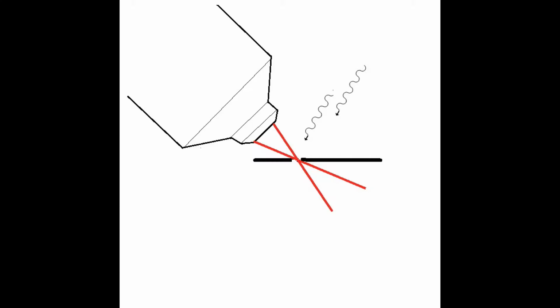By locating the smallest hole in the silver specimen and adjusting the X, Y, and Z axes on the specimen stage for the lowest possible counts, the precise analyzer focal point is obtained. If the Z height is slightly higher or lower than the optimal position, the counts will increase as the analyzer will be looking at the larger area, as shown in this diagram.